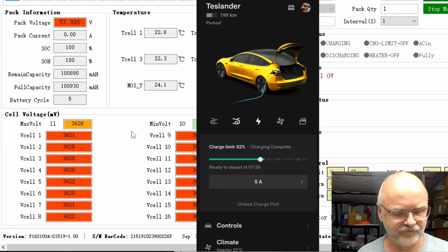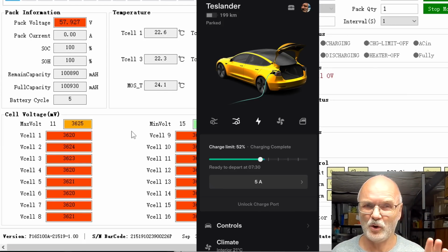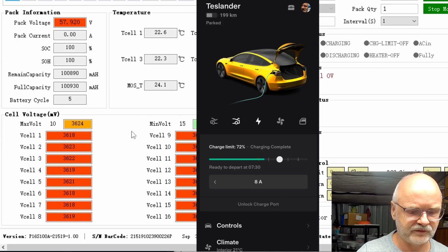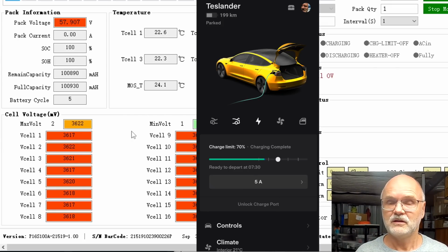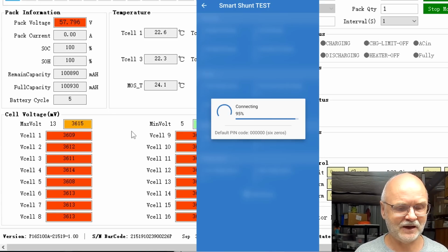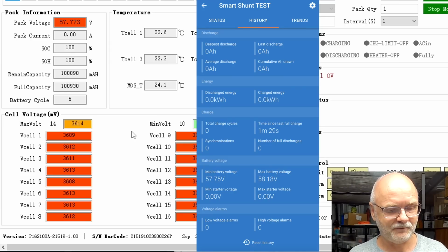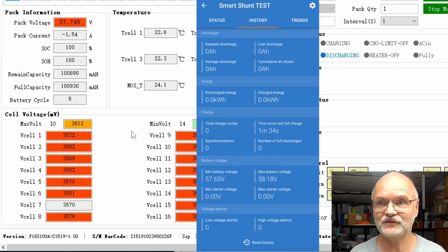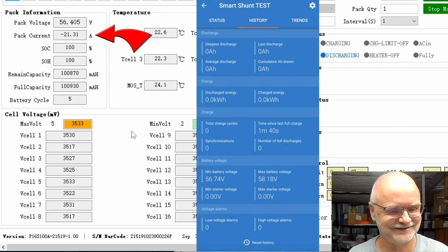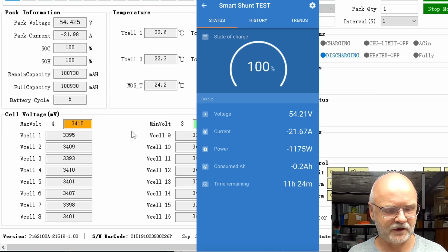Okay, set this one to 5 amps, which is our 1 kilowatt, around 0.2C, and set this one to 70% or whatever. Back into our smart shunt test, everything is on 0. Perfect conditions, and we are discharging at about 21 amps. There, we can see 1100 watts, 21 amps. It says it will run for 10 hours... ah, it's coming down now. So we should be done in about 4.5 to 5 hours or so.